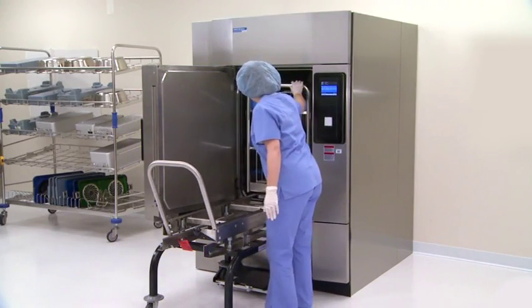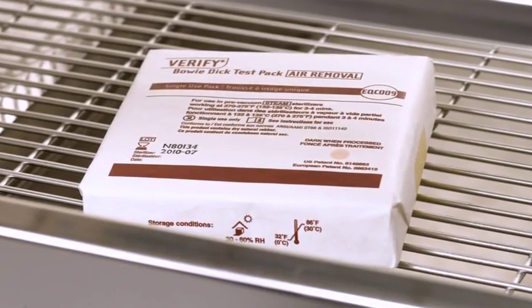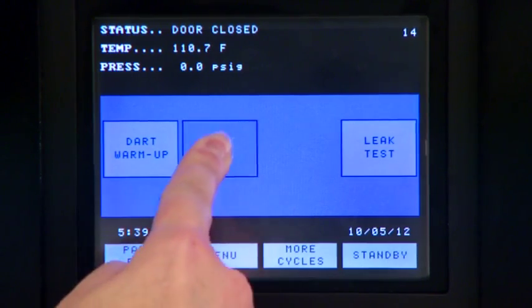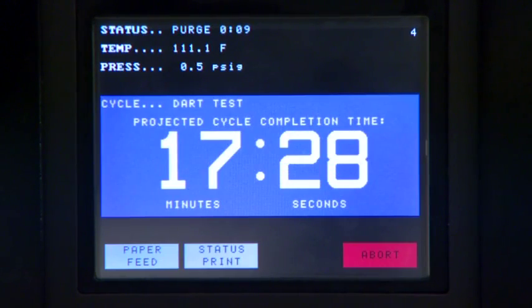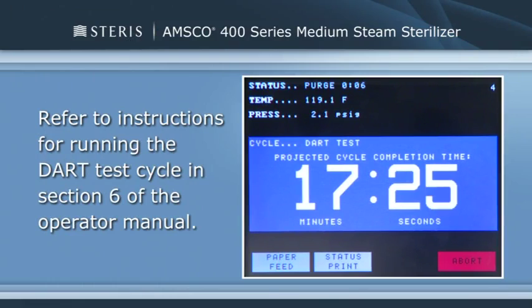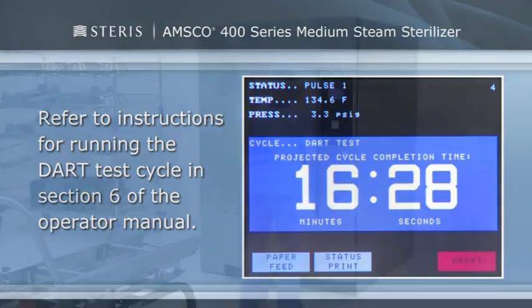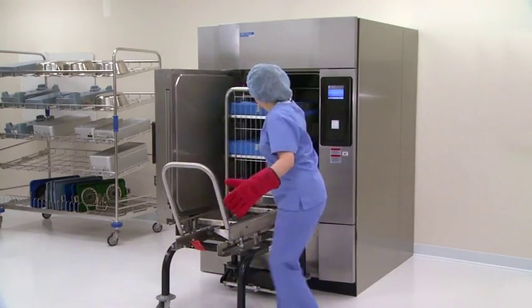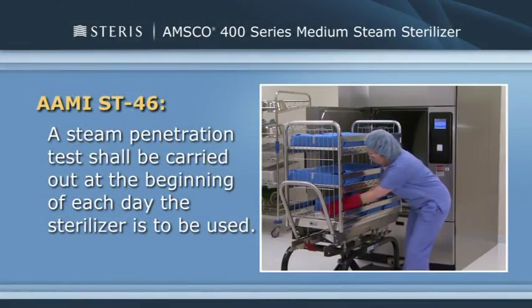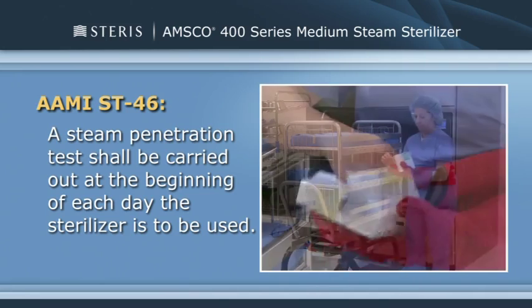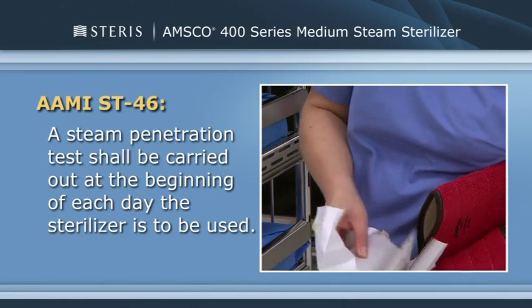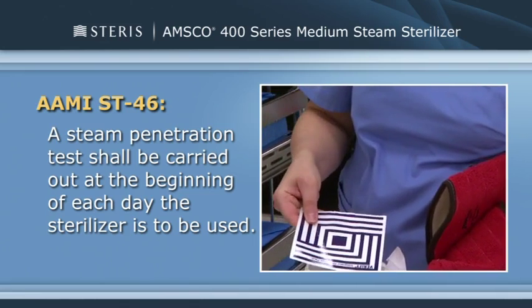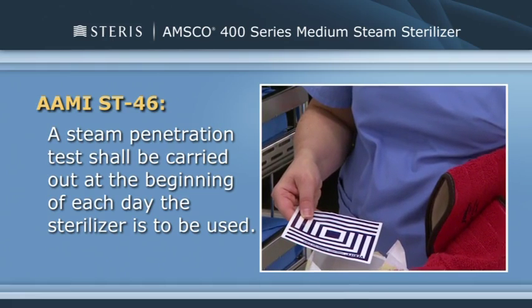Tests such as the dart or Bowie Dick are designed to document the removal of residual air from a sample challenge load. Run a dart cycle daily before processing any loads in a sterilizer equipped with pre-vacuum cycles. The first pre-vacuum cycle of each day should be used to test the adequacy of air removal from the chamber and load, so that steam can penetrate the load. It is not a test for adequate exposure to heat in terms of time at temperature. In the case of these tests, following exposure in a pre-vacuum sterilizing cycle, the pack is opened, the indicator examined, and conclusions are drawn as to the pattern of residual air, if any, that remained in the pack during the sterilization cycle. Any indication of a malfunction must be reported to the supervisor, and the sterilizer must not be used again until approved by the supervisor.